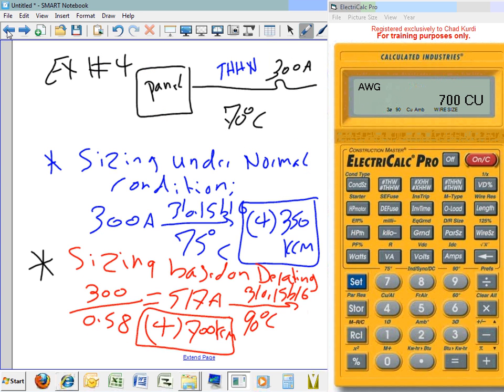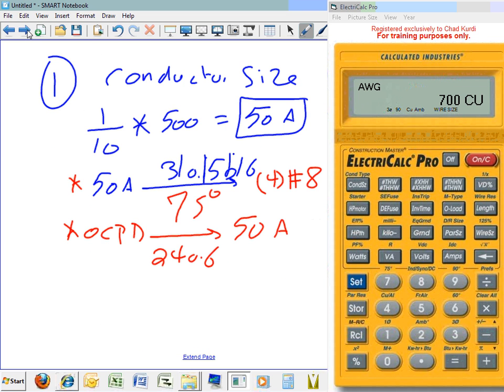So the minimum conductor that you can tap at the 10-foot rule is a number 8 conductor, and you can land it on a 50 amp circuit breaker. Remember, the terminations are rated for 75. If they weren't, then it would be number 6, and the overcurrent protection device would be 40. But 99% of the time when you tap, all the conductors and big equipment are rated for 75, good to go.